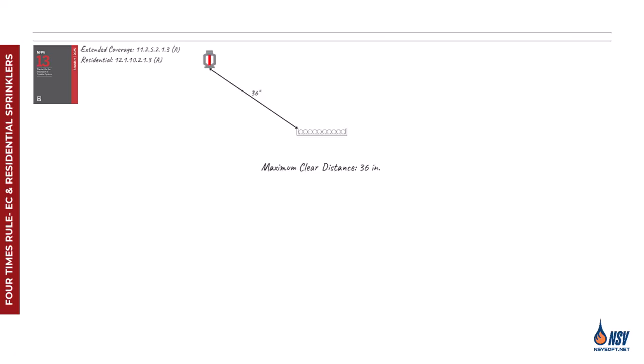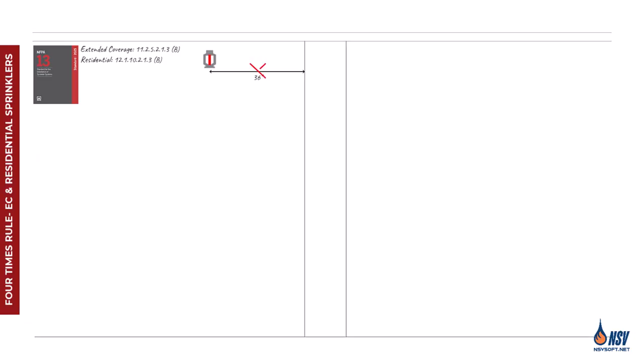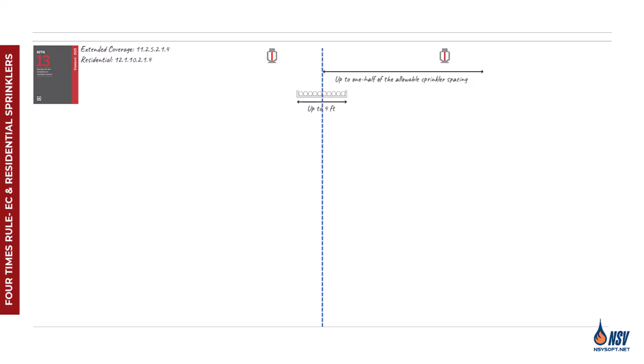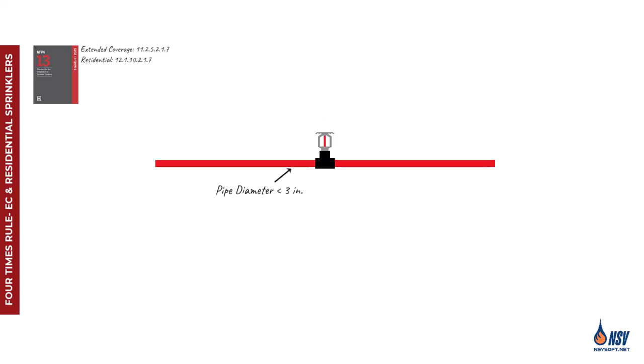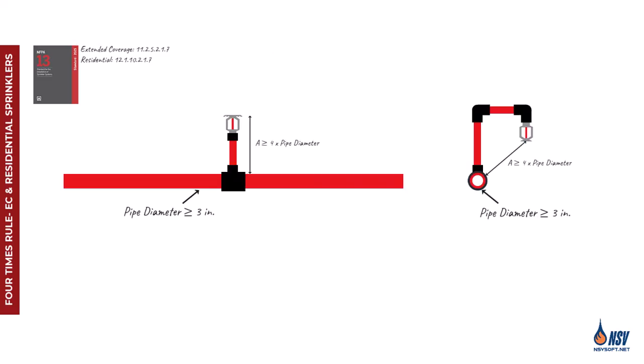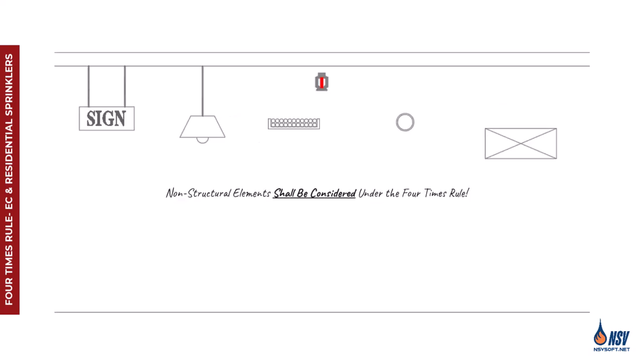For horizontal obstructions, the maximum clear distance is 36 inches. However, for vertical obstructions, there is no specified maximum distance. There are a few exceptions, as with standard spray sprinklers. Sprinklers may be installed on the opposite side of the obstruction, and pipes less than three inches in diameter are also exempt from this rule. It's important to note that the exception for non-structural members in light and ordinary hazard areas does not apply.